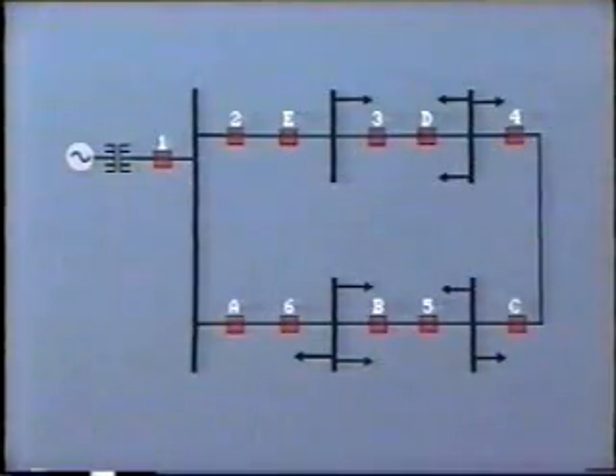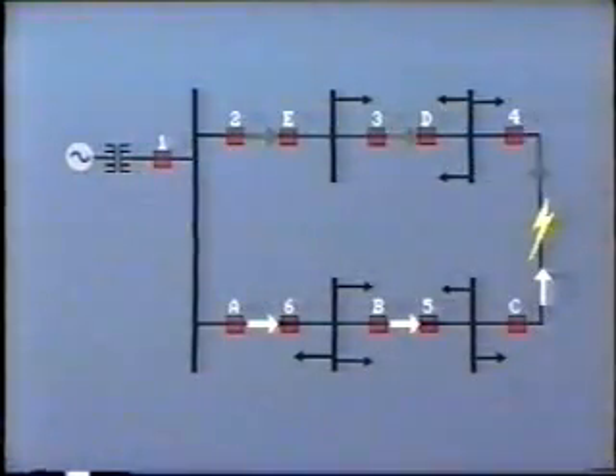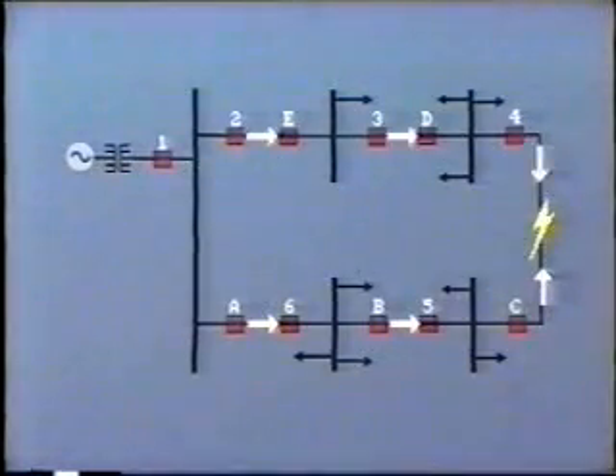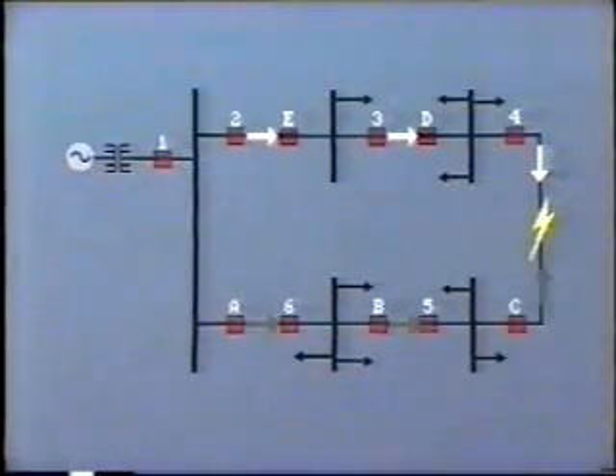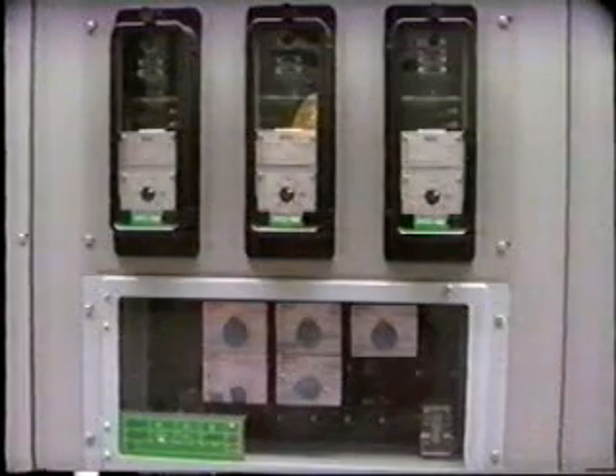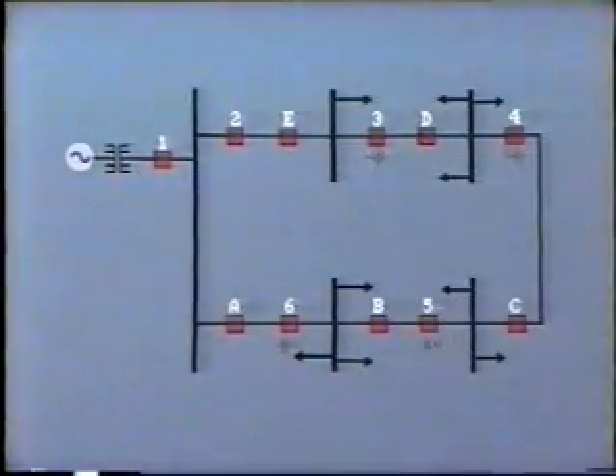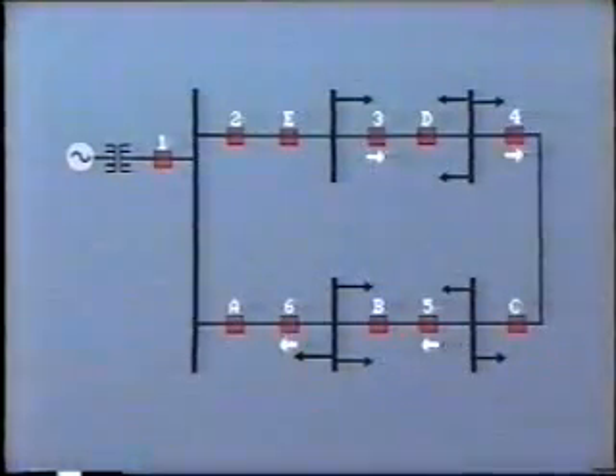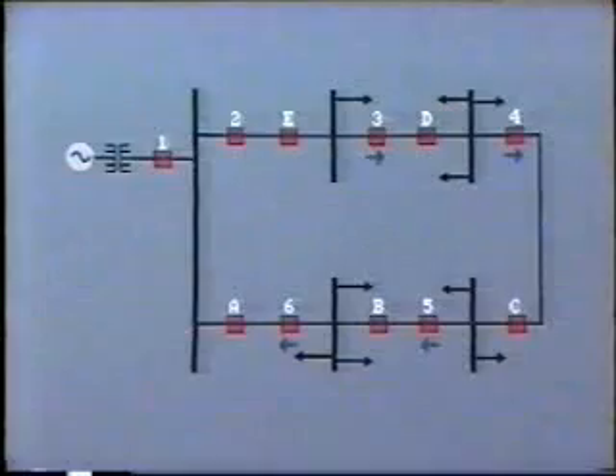In a sub-transmission loop, breakers will be located at both ends of each section of line feeding into the various buses. Now, if a fault were to occur, say, at the very end of the loop, at this point, current flows from the source to the fault in a clockwise direction along the upper part of the loop, and in a counterclockwise direction along the bottom portion. The overcurrent relays are set up to be directional with the tripping direction looking into the line. For example, for these breakers, 3, 4, 5, and 6, the directional element will trip in a clockwise direction. At breaker number 2, there will be no need for directional control, as fault current will always flow in one direction only.